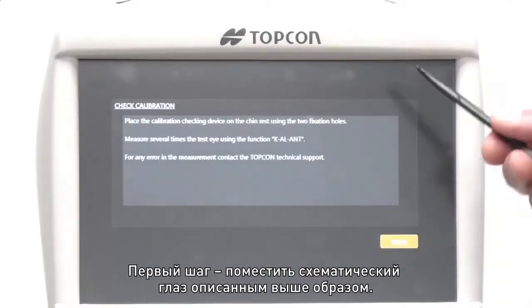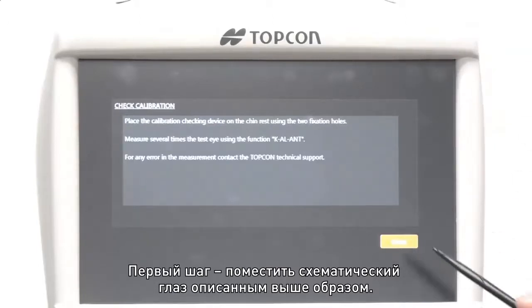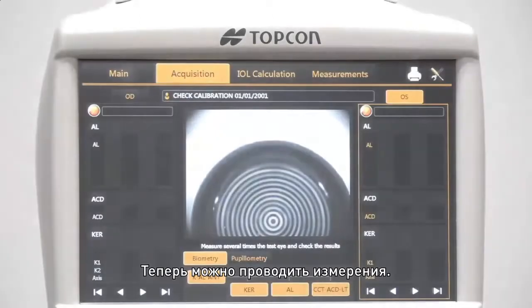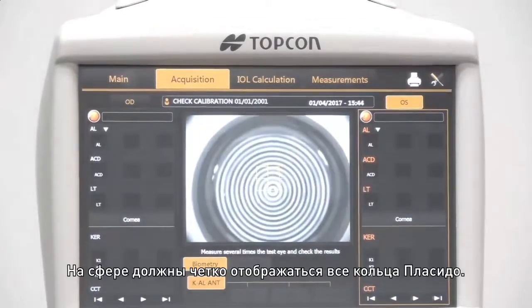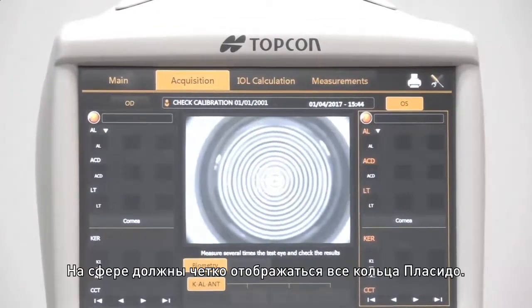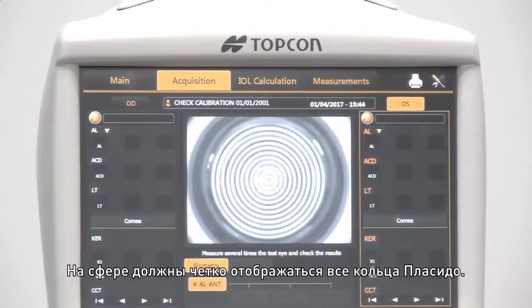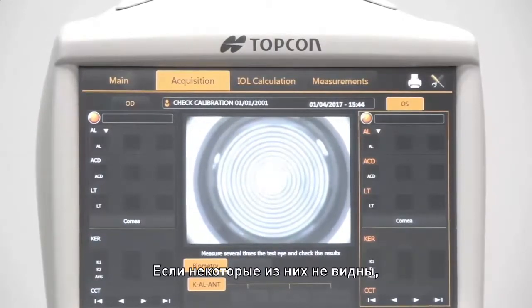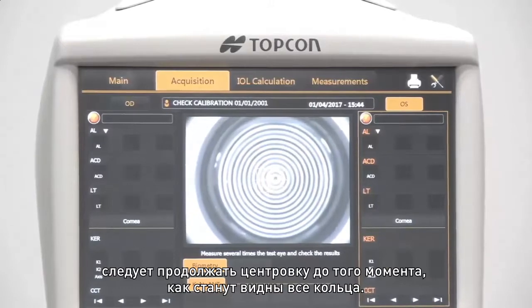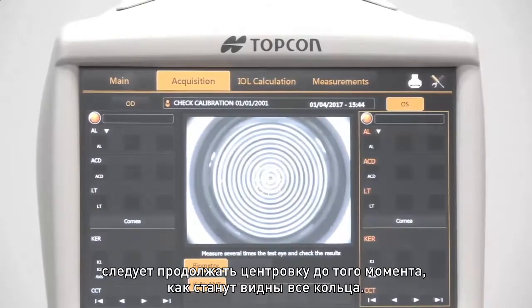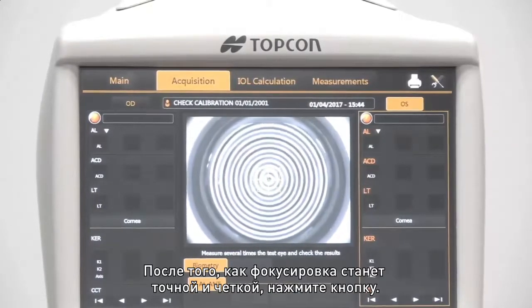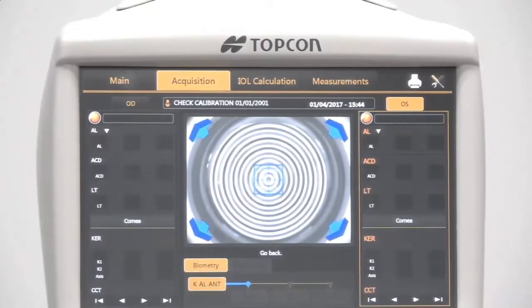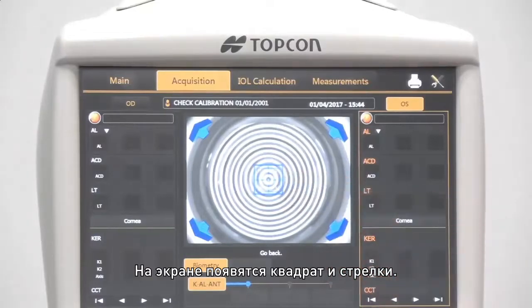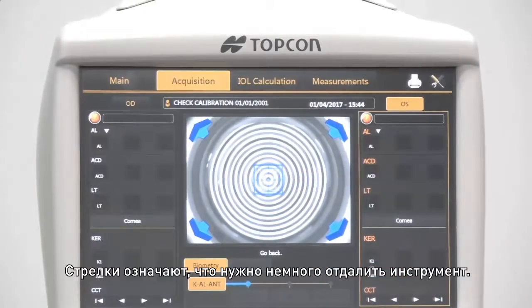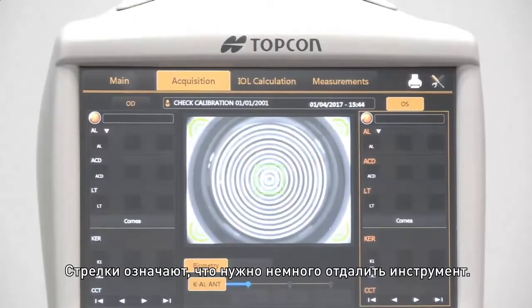The first thing it says is to place the schematic eye as we said, and now we are ready to perform a measurement. We have to have all the Placido rings reflected on the sphere. If some of them are not visible, we have to correct the centering until all of them appear. Once they are clearly focused, we press the button once and we see that the mires and the arrows are all blue, indicating that we have to move away from the target.